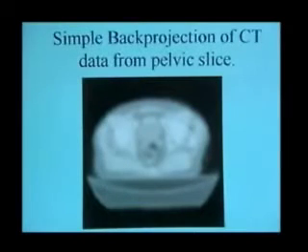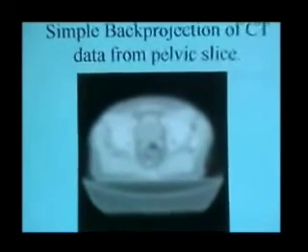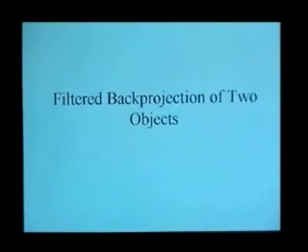However, when simple back projection is applied to real CT data, the blurring effect seems to be much more serious. There are two reasons for this. Firstly, the objects imaged in a real CT scan have a whole range of density values, whereas the squares in James' model have just one. And secondly, a much higher spatial resolution is required. Nevertheless, the technique can be improved by filtering the data before carrying out the reconstruction. And this is known as filtered back projection.